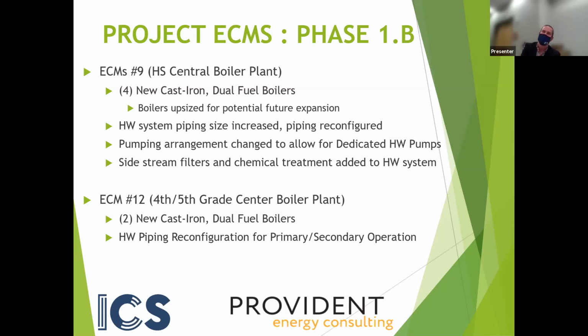Back in November we had a similar scope of work, but there are two enhancements. We've increased the size of the new boilers versus what you have now, for two reasons. One, we're adding load to the system, since part of optimizing the geothermal systems is to remove load from them. The second point is the potential for future expansion, since these boilers will last 25 plus years. We discussed this with the administration and agreed to maximize the dimensions of the space available, putting in the largest boilers we could, about 30% more capacity than what you currently have at the high school.